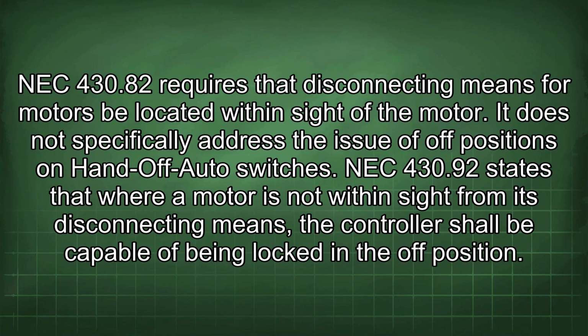NEC 430.82 requires that disconnecting means for motors be located within sight of the motor. It does not specifically address the issue of off positions on hand-off auto switches. NEC 430.92 states that where a motor is not within sight from its disconnecting means, the controller shall be capable of being locked in the off position.